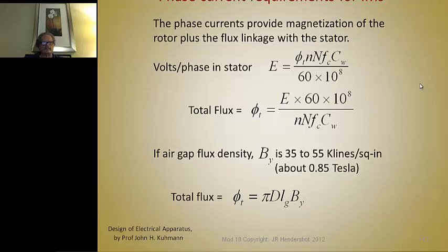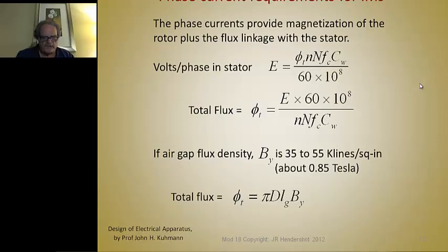The phase current requirements can be calculated, including the volts per phase in the stator. The total flux in the stator is calculated from these formulas, targeting an air gap flux density of about 0.85 Tesla, or 55,000 lines per square inch. There's also a formula for total flux.